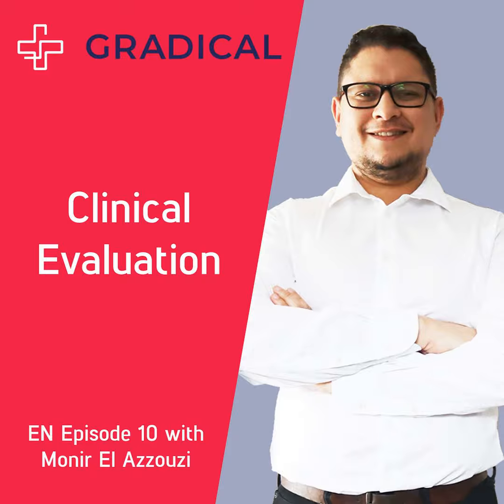This is one of the big problems of companies. They think, let me take a template, let me purchase a template, fill it in, and it's fine. No, you have to really understand clinical evaluation and also medical writing. As soon as you have done that, hallelujah, nobody can really contradict what you are providing. But understand that even if you have done a clinical evaluation, the notified body will come back, and I had that 100% for all the ones that we have published. They will come back with non-conformities about your clinical evaluation, because they are not the expert of your product.